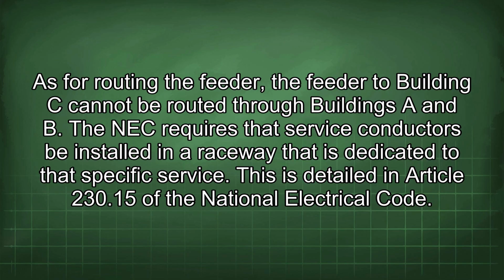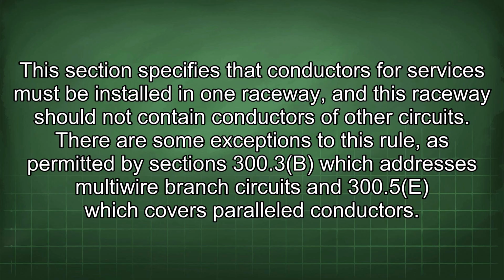The NEC requires that service conductors be installed in a raceway that is dedicated to that specific service. This is detailed in Article 230.15 of the National Electrical Code. This section specifies that conductors for services must be installed in one raceway, and this raceway should not contain conductors of other circuits. There are some exceptions to this rule, as permitted by sections 300.3(B), which addresses multi-wire branch circuits, and 300.5(E), which covers parallel conductors.